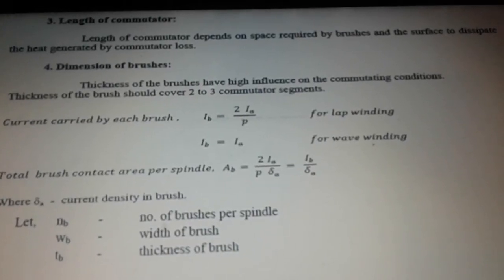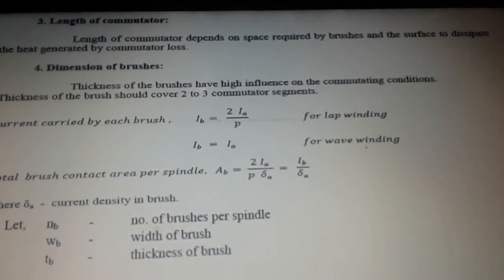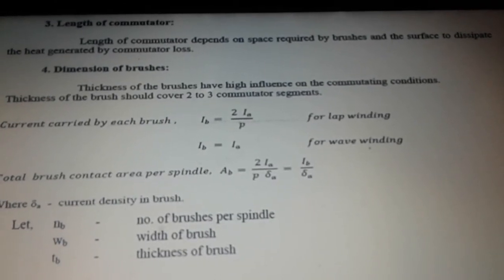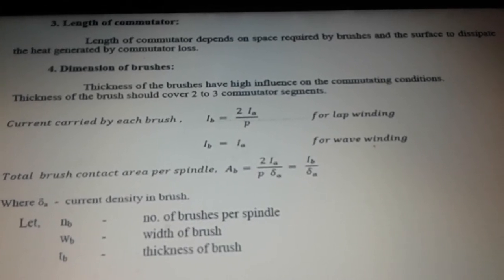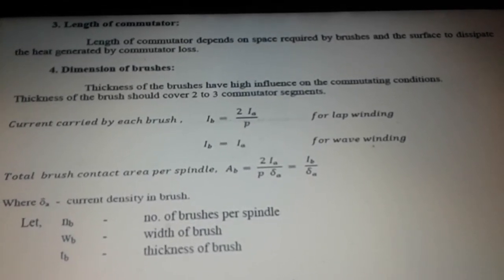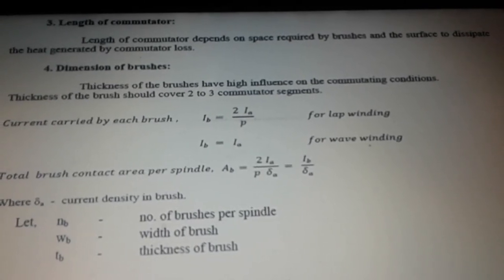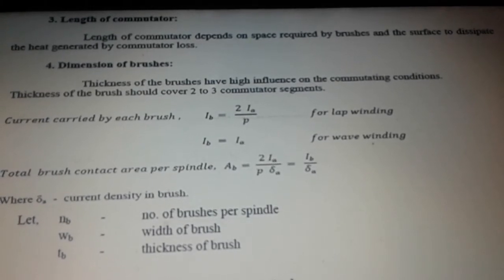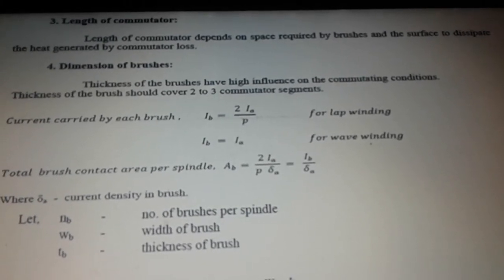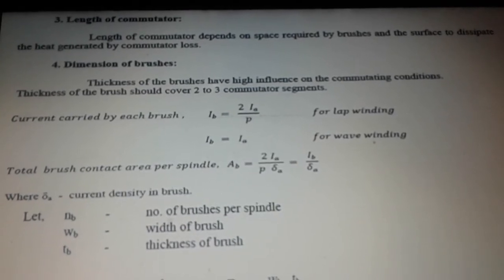Length of commutator depends on the space required for brushes and the surface to dissipate the heat generated by commutator loss. Dimension of brushes: The thickness of the brushes have high influence on the commutating conditions. Thickness of the brush should cover 2 to 3 commutator segments.